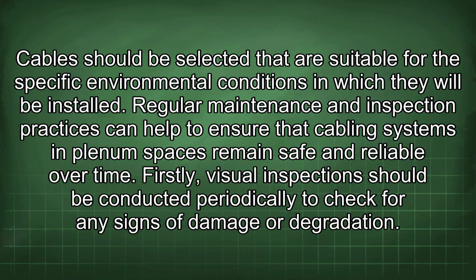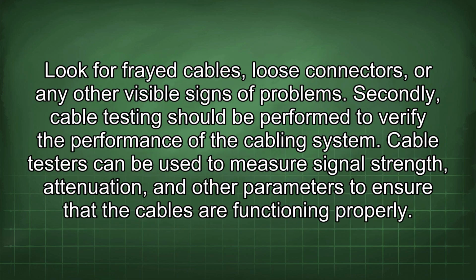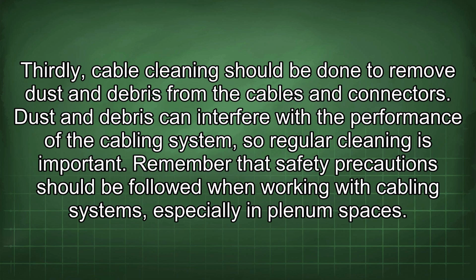Regular maintenance and inspection practices can help to ensure that cabling systems in plenum spaces remain safe and reliable over time. Firstly, visual inspections should be conducted periodically to check for any signs of damage or degradation. Look for frayed cables, loose connectors, or any other visible signs of problems. Secondly, cable testing should be performed to verify the performance of the cabling system. Cable testers can be used to measure signal strength, attenuation, and other parameters to ensure that the cables are functioning properly. Thirdly, cable cleaning should be done to remove dust and debris from the cables and connectors. Dust and debris can interfere with the performance of the cabling system, so regular cleaning is important.